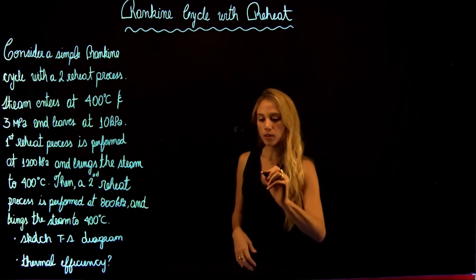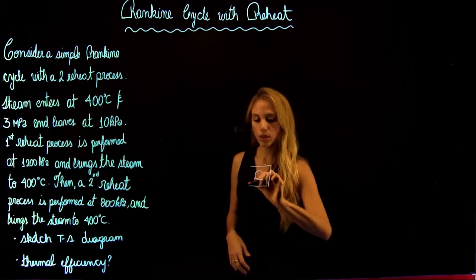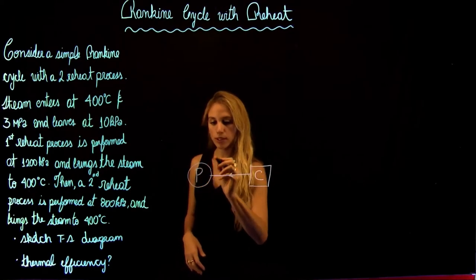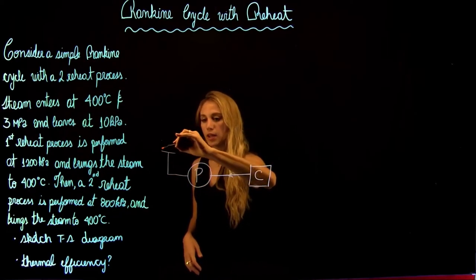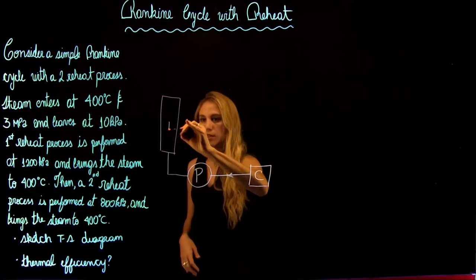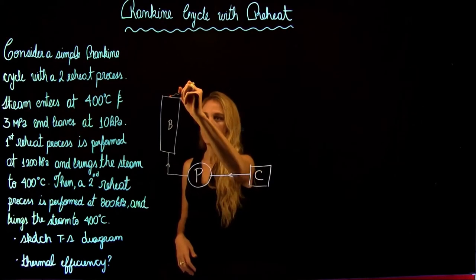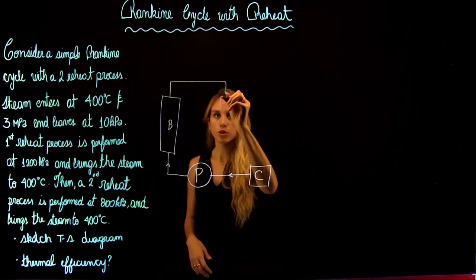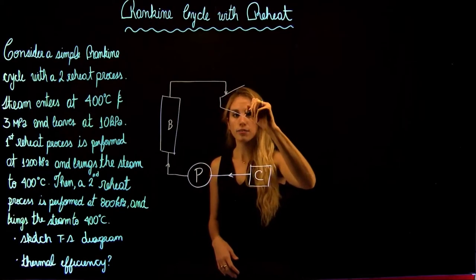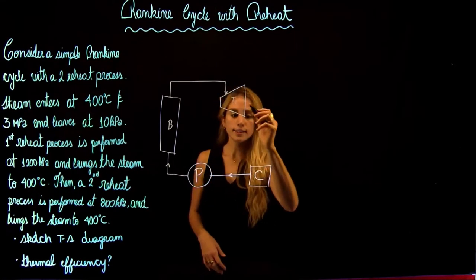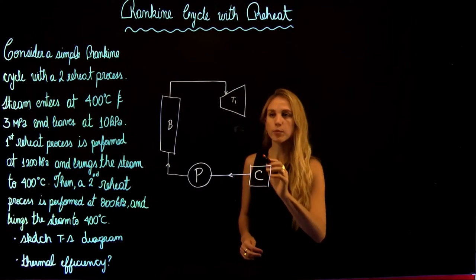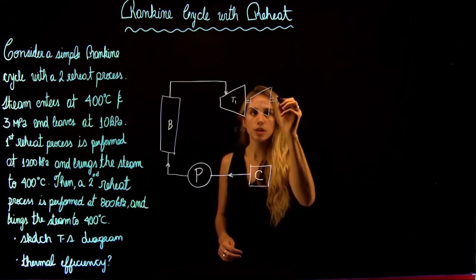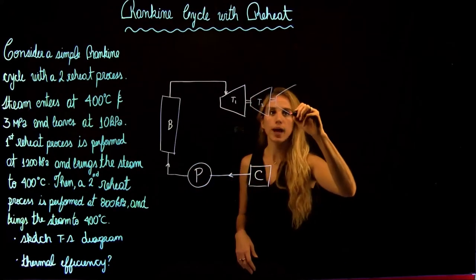This is our process diagram. The condenser is where the liquid exits and goes to the pump, where pressure increases and the compressed fluid enters the boiler. In the boiler, temperature increases to cause a phase change and the fluid leaves as steam to enter the turbine. In a simple Rankine cycle, after isentropic expansion in the turbine, steam is sent back to the condenser. In a reheat system, additional turbines are added to improve efficiency. Since we have a two-reheat process, we are going to have three turbines.